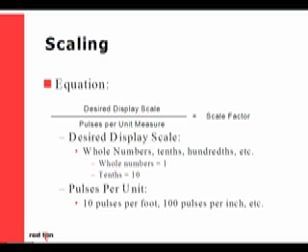Our equation for determining the scale factor is desired display scale over pulses per unit measure. The desired display scale tells the counter how accurate we want our value displayed, whether it is in whole numbers, tenths, hundredths, or so on.